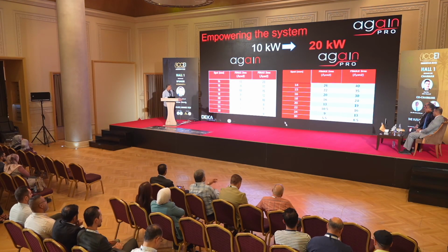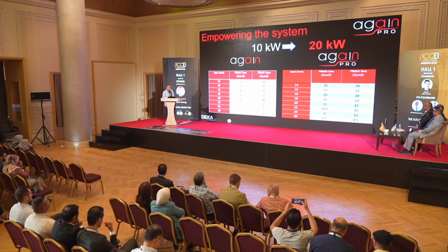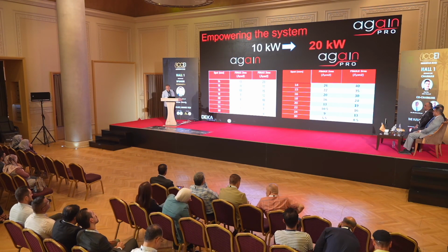In Again Pro, we can reach up to 20 joules per square centimeter because of the mega power of the device. We can also compare the old version and the new version. With 30 millimeters, here gives me 4 joules maximum for Alex, and here 8.5 maximum in 30 millimeters for Gentle Pro.